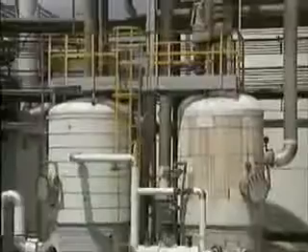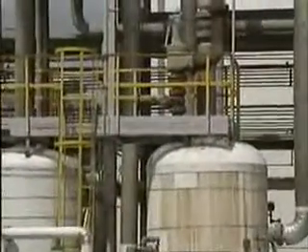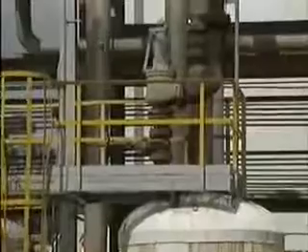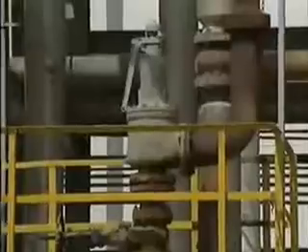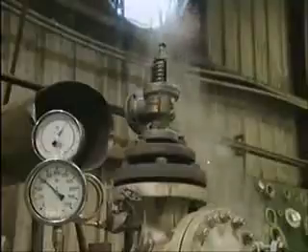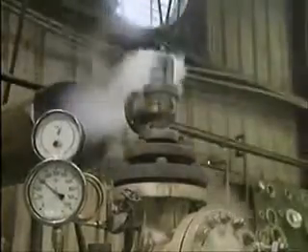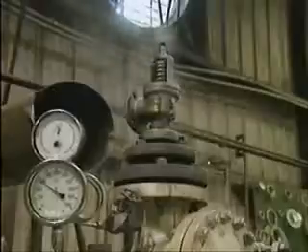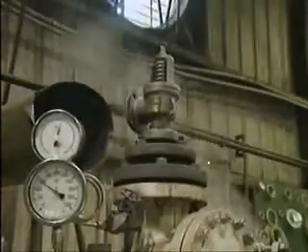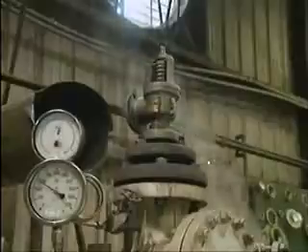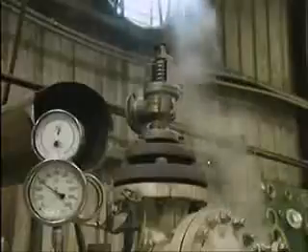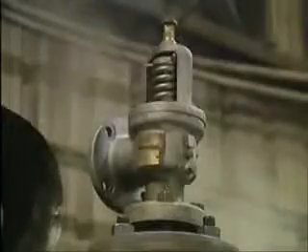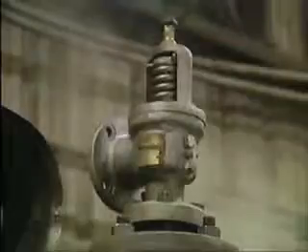Safety valves are commonly used on gas or steam lines because the volume of the gas or steam increases as pressure decreases, and a gas that's under pressure may expand to a tremendous volume when the pressure is relieved. One thing all safety valves have in common is that they open wide very quickly and stay open until the system pressure drops a predetermined amount below the point at which the valve is set to open. The valve allows a large volume of gas to escape as pressure is reduced. In this part, we'll look at a huddling chamber safety valve.